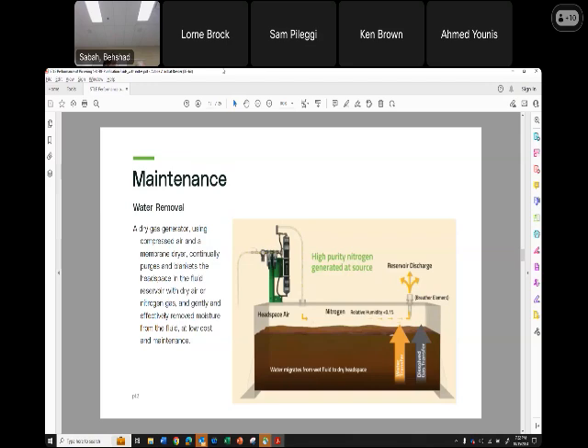Okay, so Peter showed you this already. This is dry nitrogen gas being generated and blown across the reservoir and exhausted. And this technology is incredibly effective. Like we turned it on, we see water drop very rapidly, and very often Mike has to call operation to tweak it back, we're getting too dry. And very often we have to turn it off. So I'm actually quite surprised at how effective this is at drying our fluid.